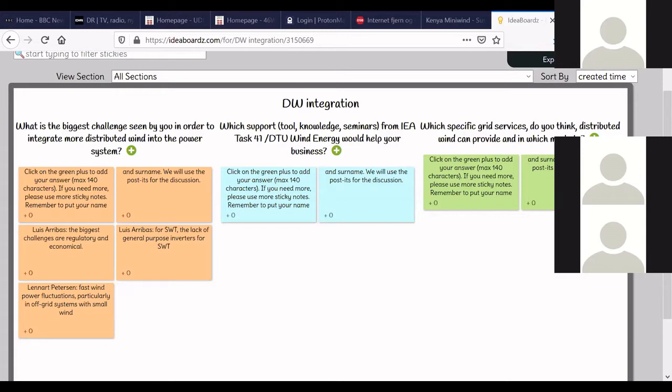Of course, that levels a bit out if you're on the megawatt scale. Sure, yeah. And of course, if you're trying to run a system without, for example, a diesel generator, but you let the battery take up the fluctuations, then the batteries themselves have problems with premature aging. But batteries also have ramping limitations, especially the flow batteries. They cannot ramp that fast anyways. So that would not also help.